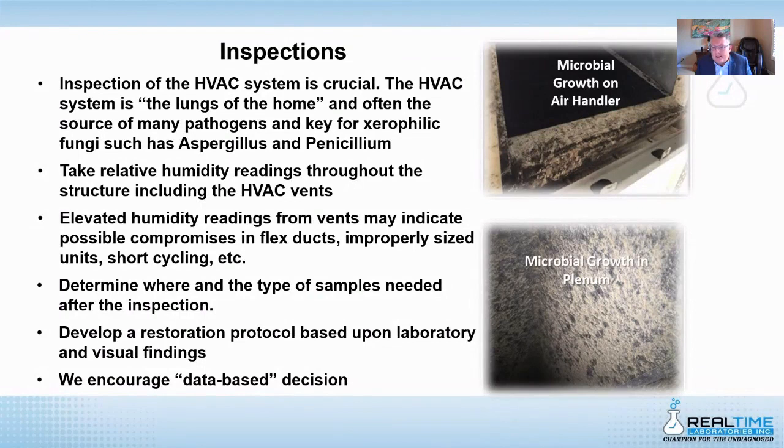We'll wind up getting the heat. We'll have the adhesive on the flex duct will separate, or we'll get palmetto rats or something along those lines that may chew holes, or there's tears or penetrations in that flex duct. So that can actually introduce contaminated and certainly elevated moisture air from the attic into the structure. If you're not testing the air coming out of your HVAC vents, it's really difficult to understand where elevated humidity is coming from. So we encourage you to certainly take a look at that.